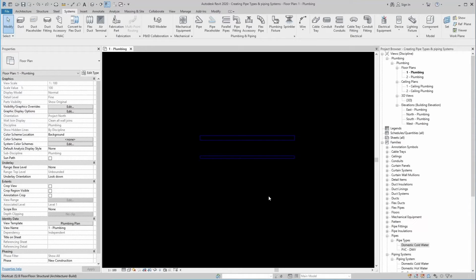In a piping system, we must know the pipe material. It's called the pipe segment. For example, we need PPRC material for the cold and hot water system, UPVC for the sanitary system, MS seamless pipe for the fire water system, and copper for the refrigeration system. Similarly, every piping system has a different material.